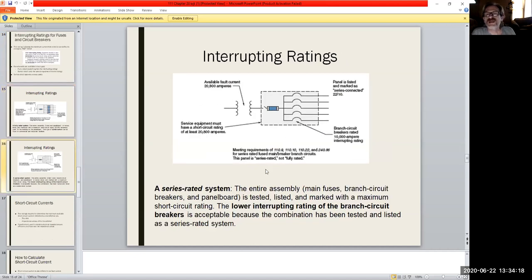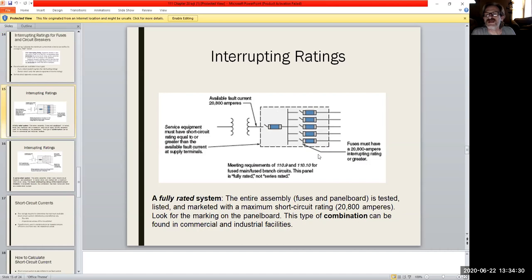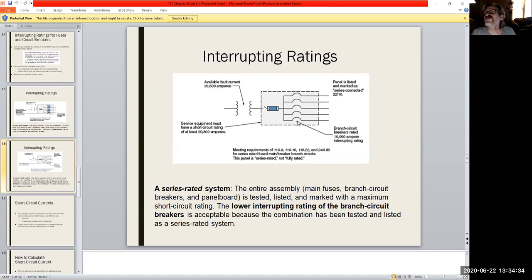Now you can see that this is laid out a little differently than this here, basically meaning that we're not fused anymore, protecting it like this. We're really just down to what the individual devices themselves can handle, and they're the ones that have their ratings on there, and that's what we expect to deal with any problems that may occur. So all in all, you usually don't deal with the series rated system. You can, but very typically you go with the fully rated. But you can have a lower interrupt rating with the branch circuit breakers, because the combination has been tested and listed, and because it is a series rated system. As long as you have it in the hands of somebody that knows what they're doing on a regular basis, then you should have no trouble with that.